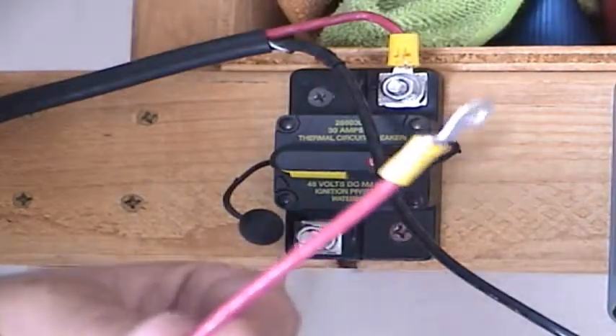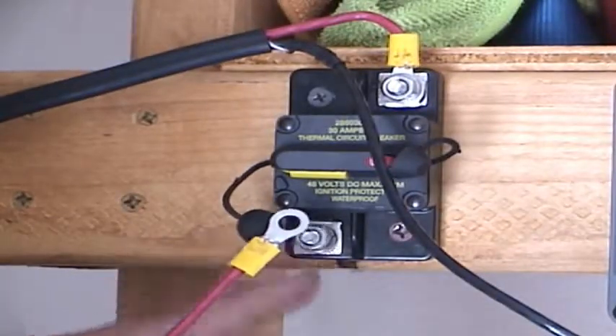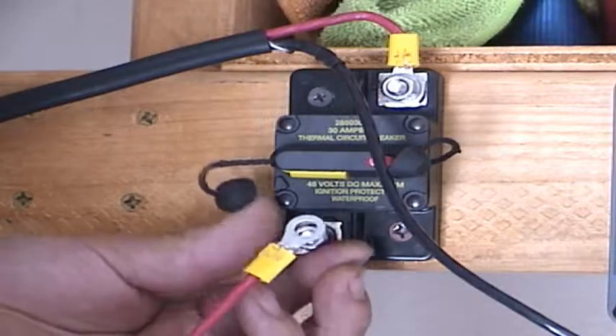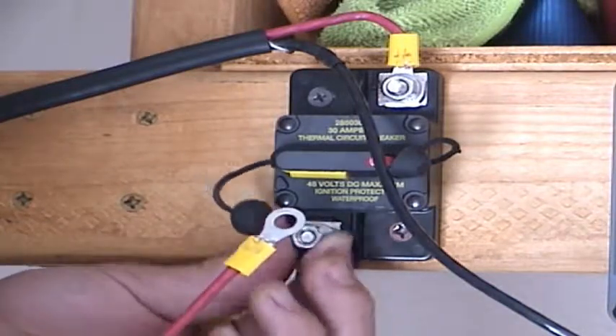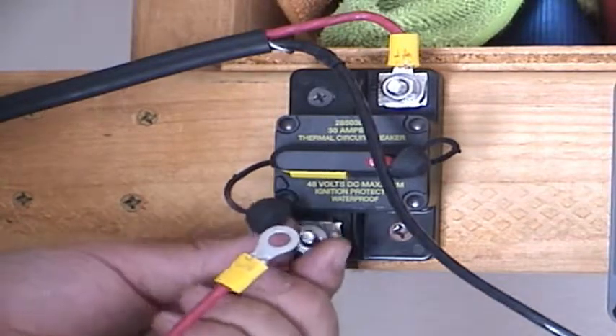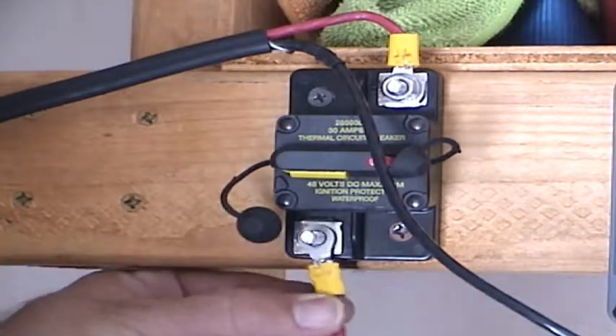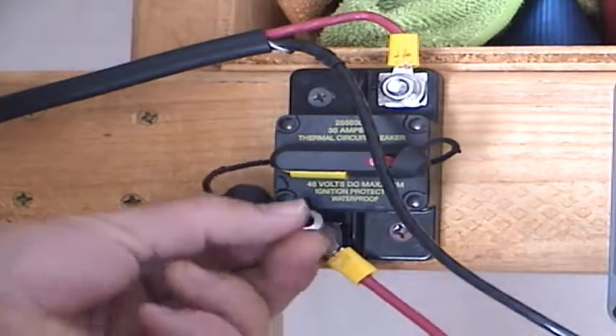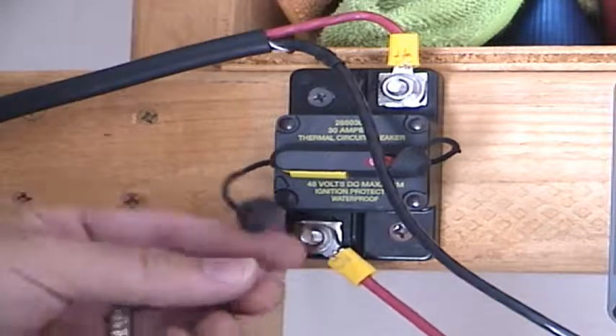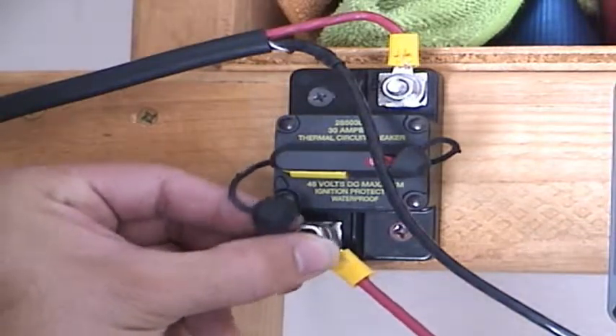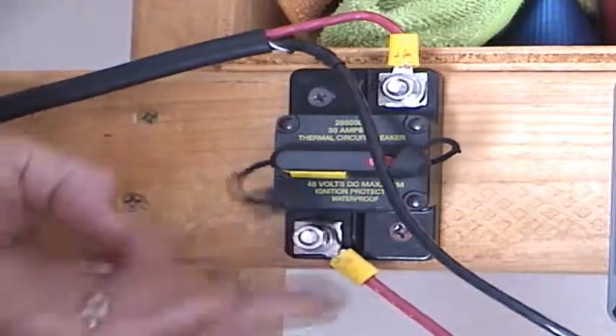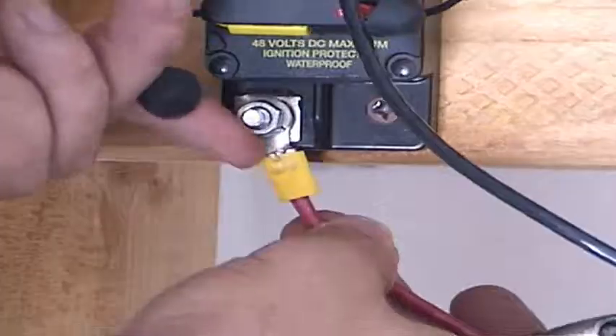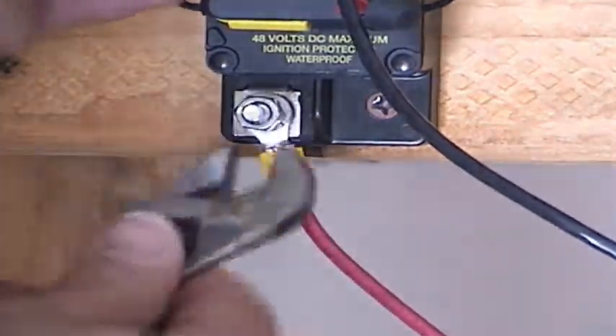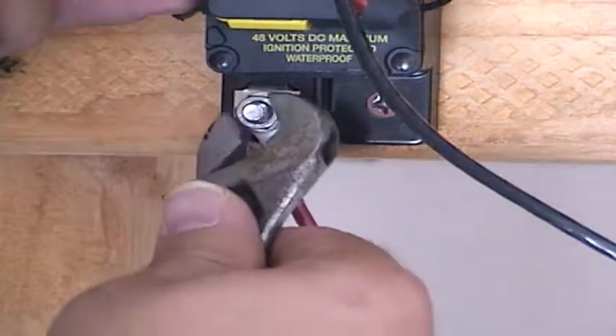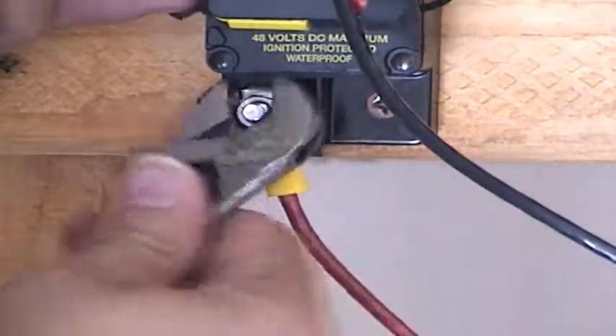Okay, now we're going to take our 8-inch piece of red 10 gauge wire. We're going to connect the ring terminal to the bottom terminal of the circuit breaker. Let's remove the nut and the lock washer. Insert the ring terminal in place. Replace the lock washer and the nut. And then go ahead and tighten the nut. Then we'll grab our wrench, tighten it completely until it's nice and snug.